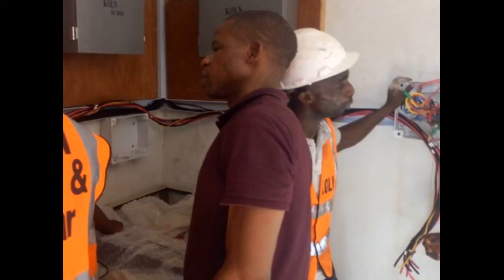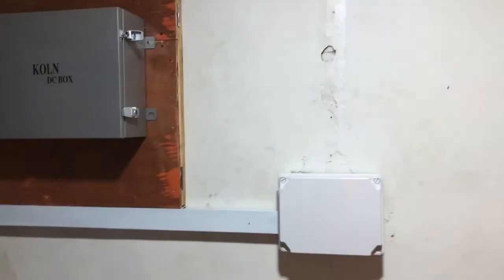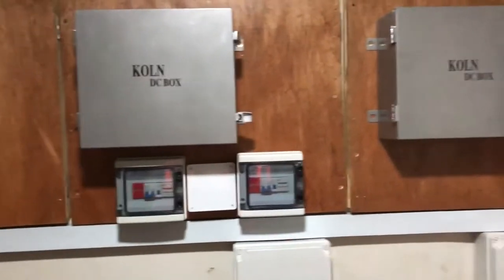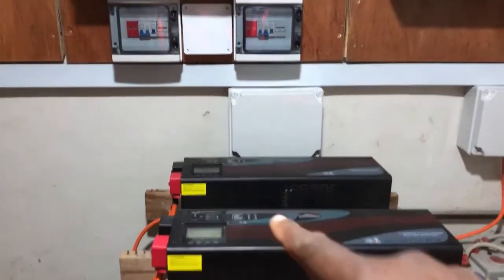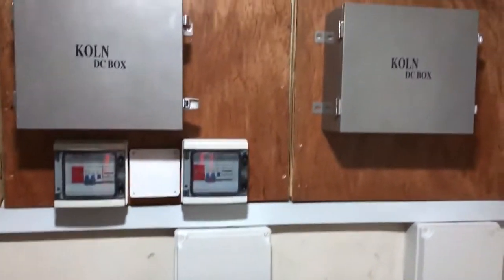And with regards to the grid cables, this thing has now been finally sorted out. We've unpicked all the wires, as you can see there, and actually matched the cables from the inverters to the 3 phases on the armored cable, as well as the grounding cable, and we have sent that all the way down to the main grounding conductor and covered it nicely in this enclosure box that works quite seamlessly with the trunking. Beautiful installation, 2 AC boxes for 2 inverters, currently up and running.